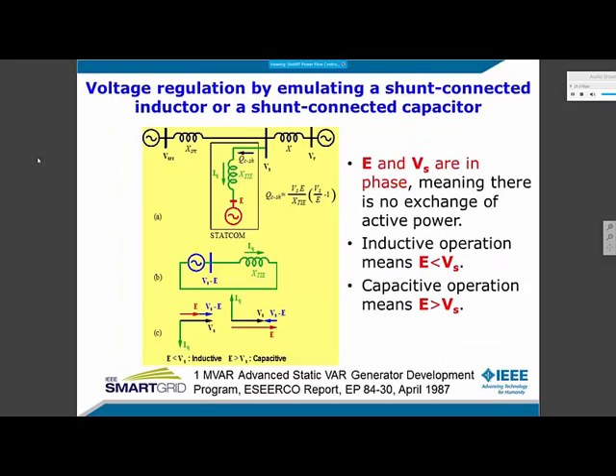Now, it is an old idea. This has been used in the synchronous condenser for over 100 years. The synchronous condenser can operate as a virtual capacitor or a virtual inductor. Why virtual? Because the actual compensation is the voltage. This voltage is the back EMF of the motor. By varying the field current, this back EMF can be made lower or higher than the line voltage. For a lower voltage, the lagging current emulates an inductive effect, and for a higher voltage, the leading current emulates a capacitive effect. So this inductor and capacitor effect actually makes the bus voltage, the voltage at the point of common coupling, regulated. And since there is no significant amount of active power flow into the machine, the voltage inside the machine and at the terminal are in phase. The response of this machine-based operation can be hundreds of milliseconds, which may be adequate in most applications.